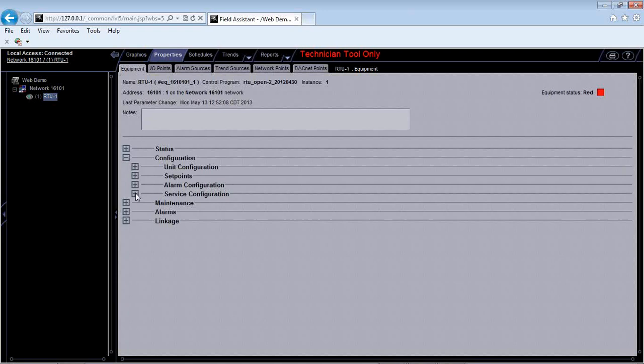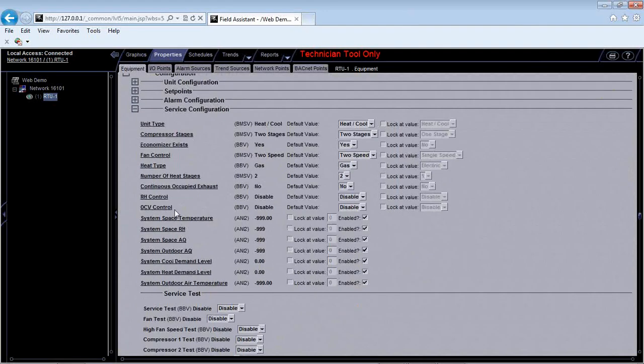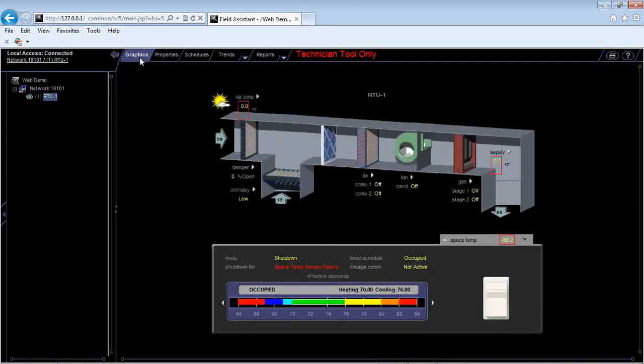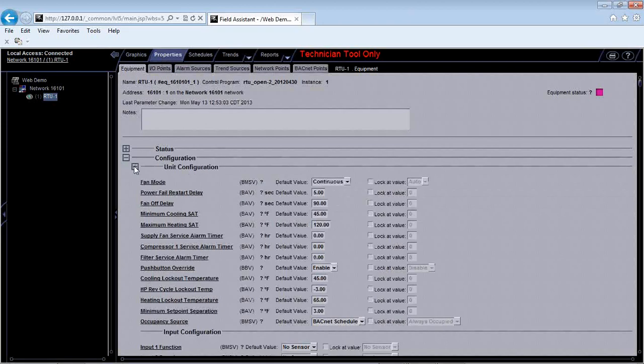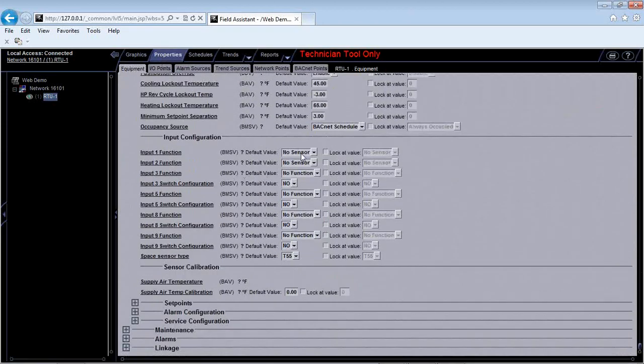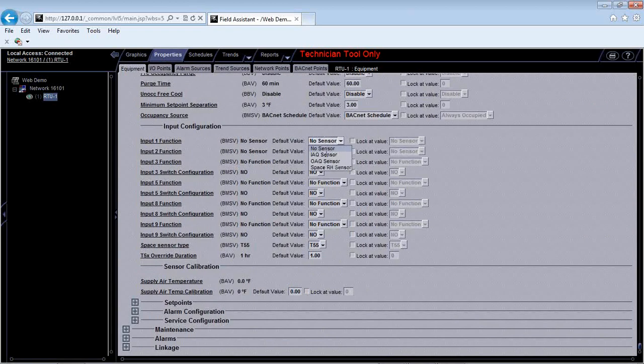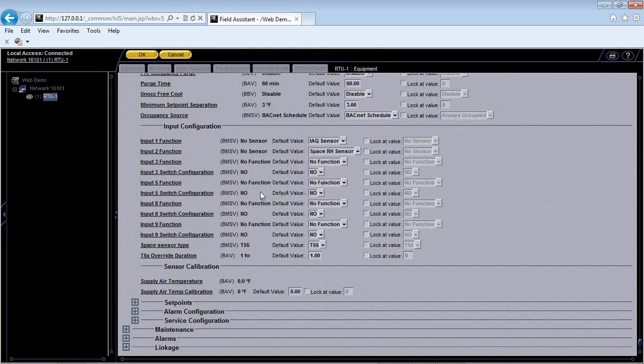Let's say that I configured I want to do demand control ventilation or relative humidity control. I would have to enable these 2 devices here. I hit OK. And now I will be monitoring my relative humidity and CO2. What I forgot here is I actually have to put the inputs for those values as well. So if you remember in Properties, Configuration, Unit Configuration, you actually have to tell it where it has its sensors. So I want to say that I have an IAQ sensor and a relative humidity sensor because I have a humidifier and a CO2 sensor in the space.